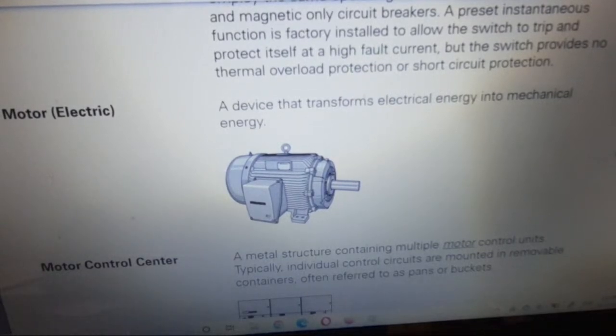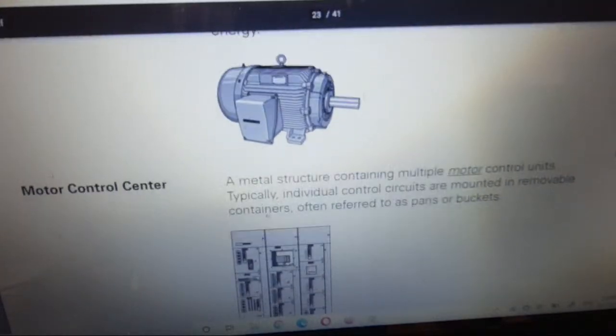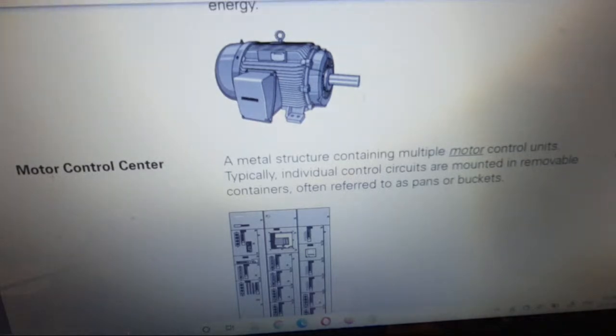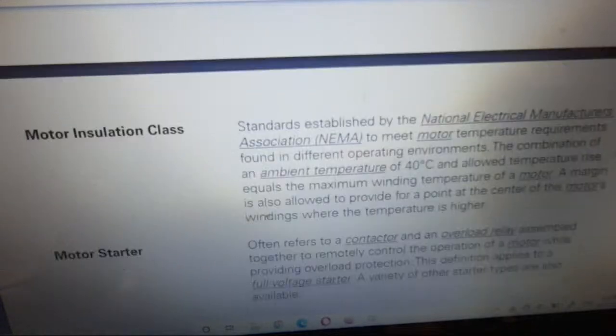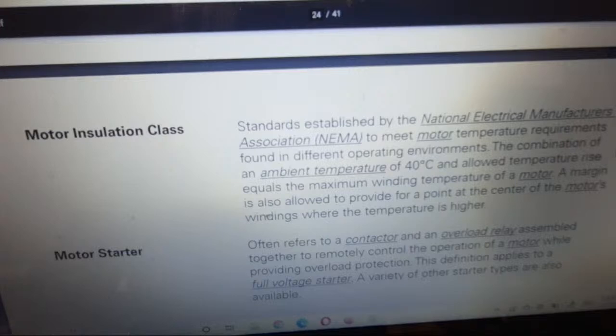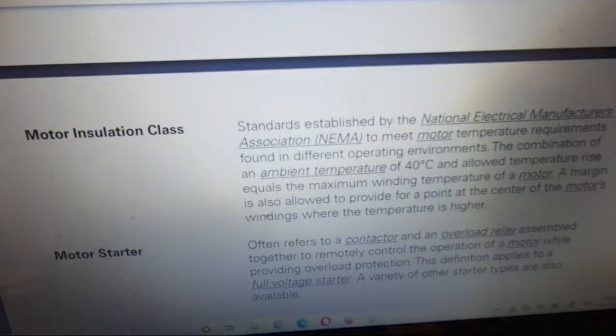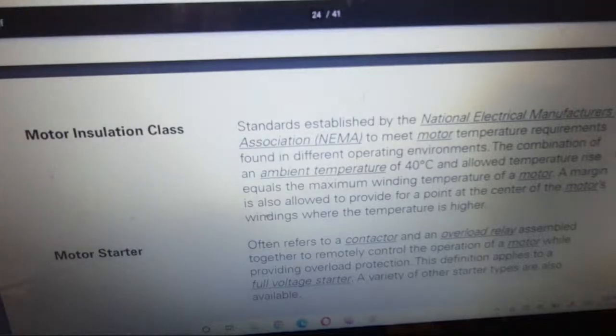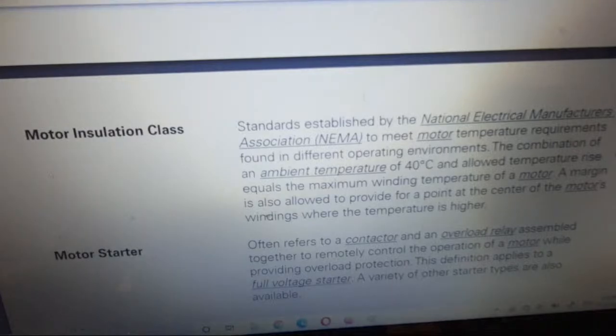Motor control center: a metal structure containing multiple motor control units. Typically, individual control circuits are mounted in removable containers, often referred to as pans or buckets. Motor insulation class: a standard established by the National Electrical Manufacturers Association, NEMA, to meet motor temperature requirements found in different operating environments. The combination of the ambient temperature of 40 degrees and the allowed temperature rise equals the maximum winding temperature of the motor. A margin is allowed to account for the point at the center of the motor winding where temperature is higher.